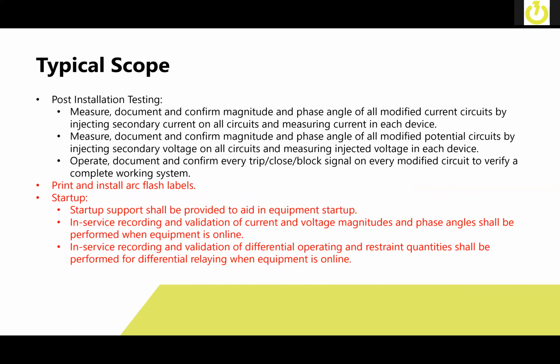The other thing we recommend is printing and installing arc flash labels. And then during startup, support provided in aiding in equipment startup. If you have any questions about the relaying, about the changes, the control schemes, that's a good time to answer those when the operations personnel are actually in the process of starting up that equipment. That is usually when we see the most questions. We also recommend that you do in-service recording and validation of all current and voltage magnitudes and phase angles with the online equipment, along with differential operating and restraint quantities for any differential relaying.